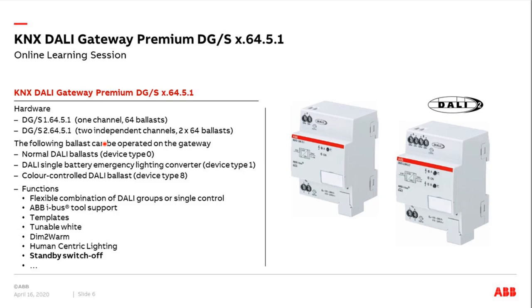Normal DALI ballasts from device type 0, single battery emergency light converters of device type 1, and color control DALI ballasts for DALI control device type 8 are also supported. Both DALI gateways are DALI 2 certified and offer extensive functions such as templates, tunable white, dim-to-warm, human centric lighting, and of course the standby switch-off covered today.